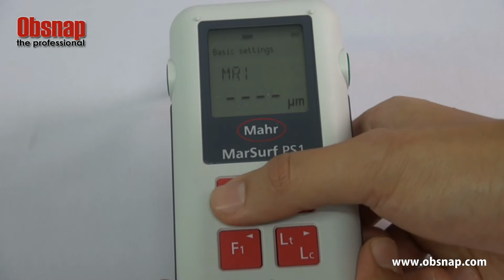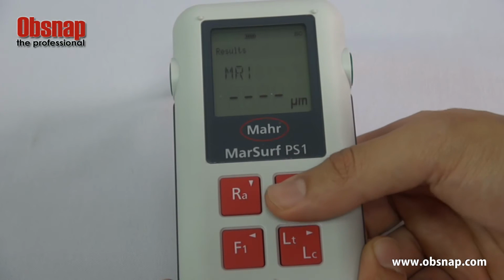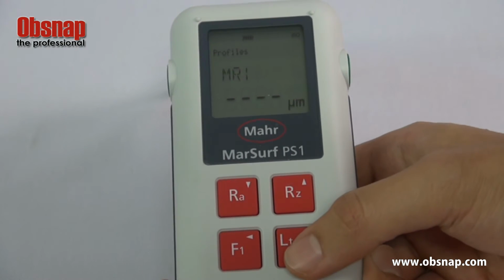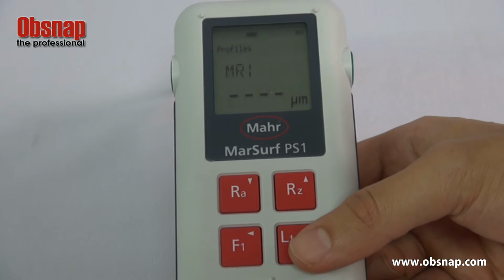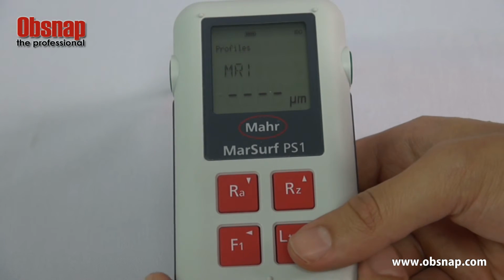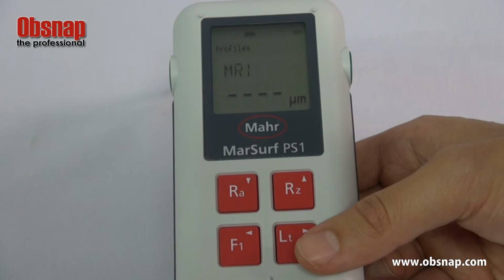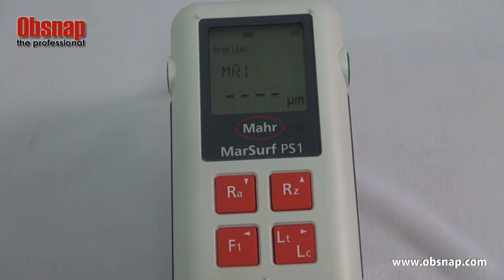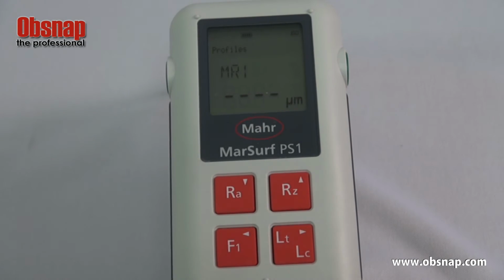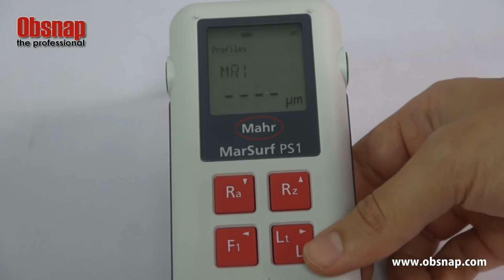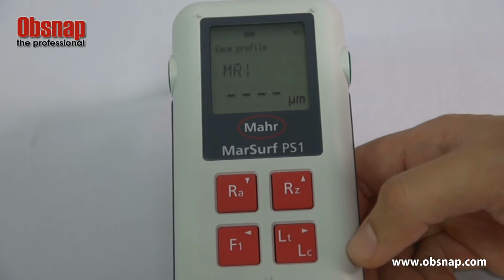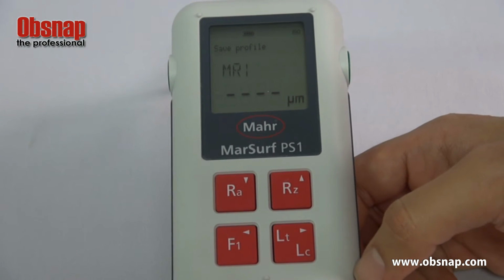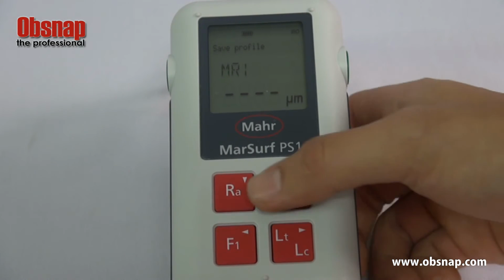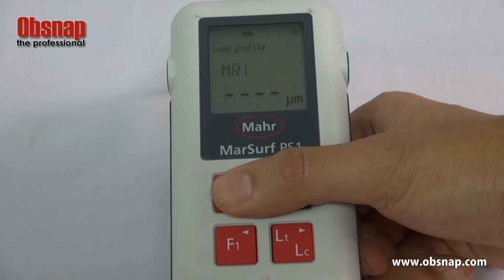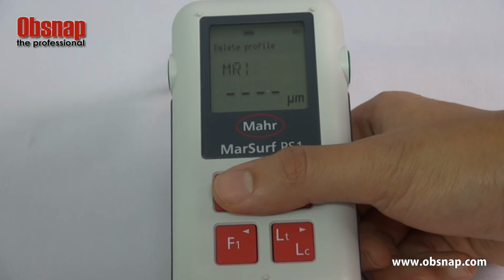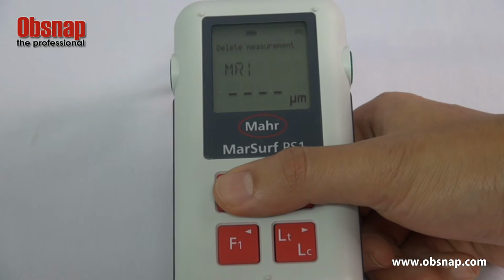So escape, back out to the profile and result. Profile and result is actually the same. Profile is the profile, and result is just the txt file of the value, or value only. For this PS1, it is able to store up to 15 profiles and 20,000 results. So for profile, you can click in the save function, you can choose. Save profile means that it will save the current result, the current profile that you obtain. Load profile and delete profile. So just load them or delete them. Delete measurement, delete what you have measured.